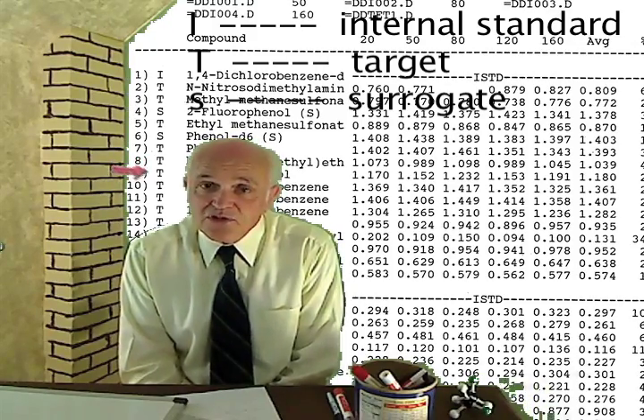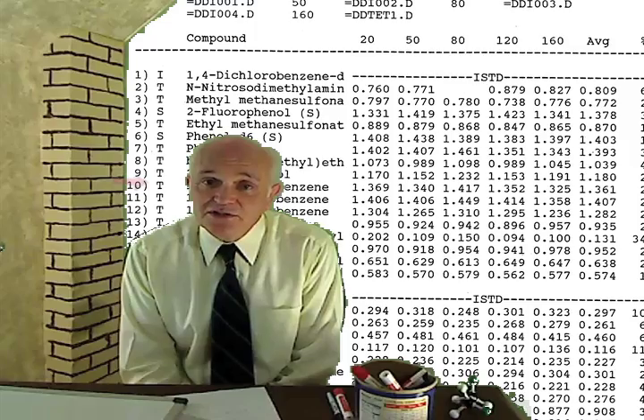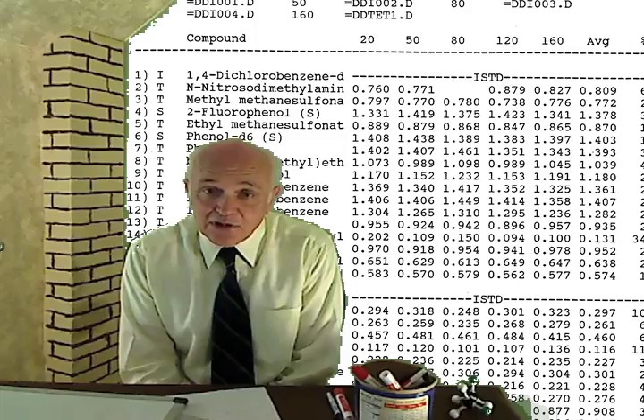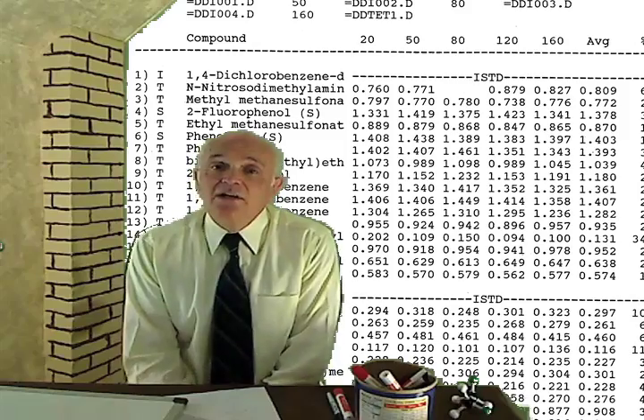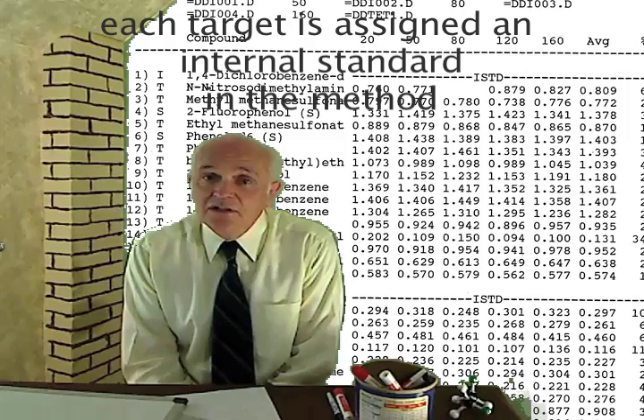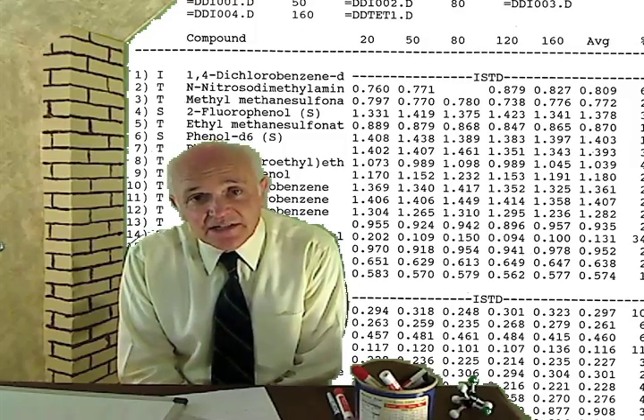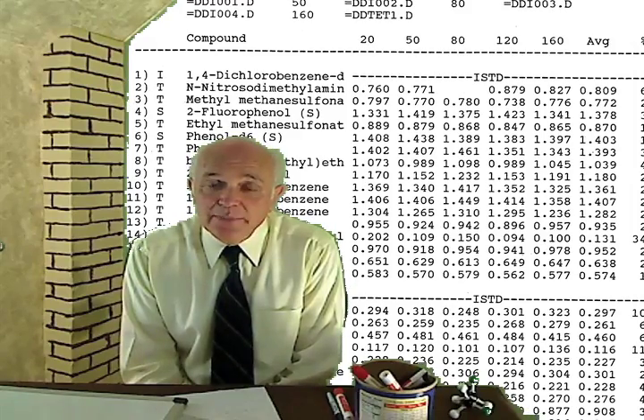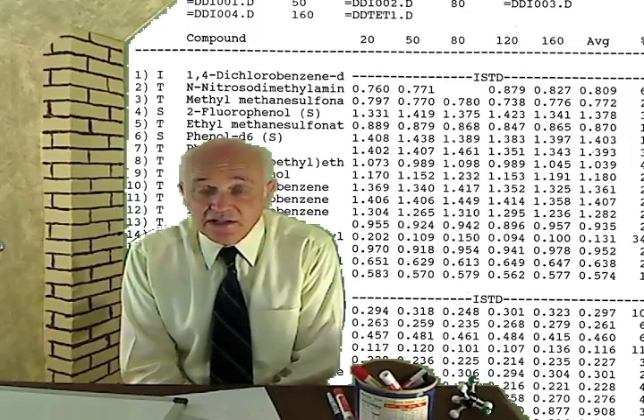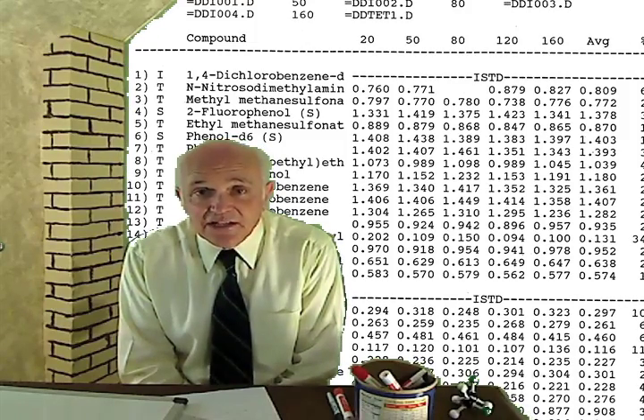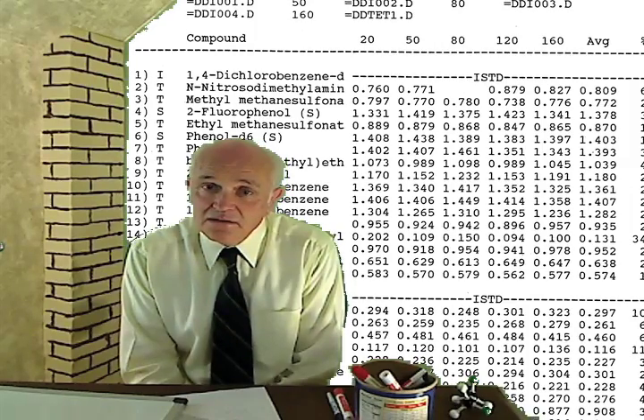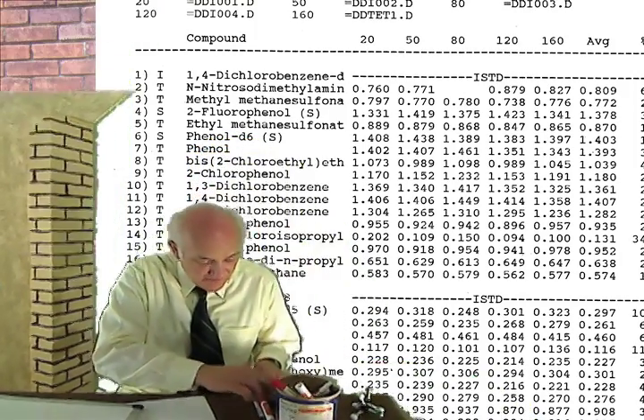The method for the 8270 consists of 70 peaks identified in the method, located to their approximate position on the chromatogram, along with six internal standards also named and located. The method requires five calibration points at 20, 50, 80, 120, and 160. The operator makes a standard at each concentration — the 20 standard is 20 of everything, including the surrogates — and all five samples are analyzed as standards.